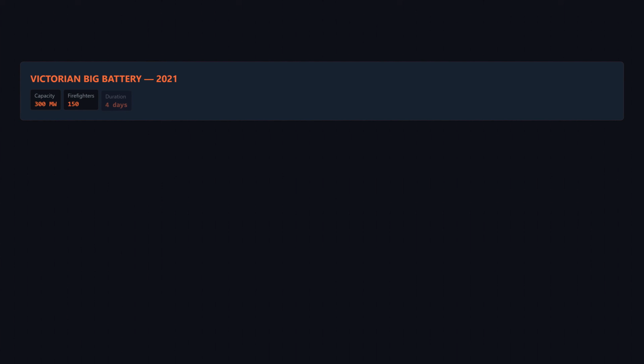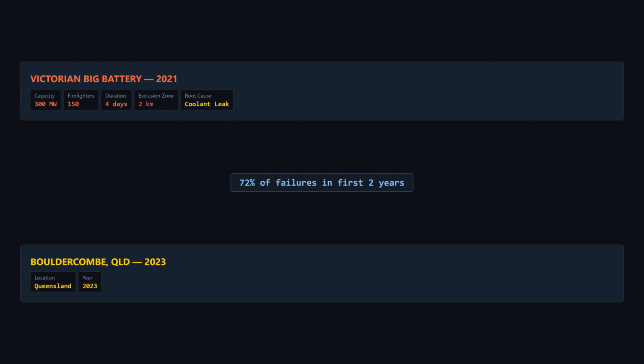July 2021. Victoria's Big Battery near Geelong. A 300 megawatt Tesla Megapack installation, one of the largest in the world. During commissioning, a coolant leak in one Megapack triggered thermal runaway. The fire spread to an adjacent unit. 150 firefighters responded. It burned for 4 days. Two Megapacks were destroyed. The CFA found that the fire couldn't be extinguished. They had to let it burn out while protecting exposures. Toxic gas emissions forced a 2-kilometer exclusion zone. A year later, Queensland's Bouldercombe BESS caught fire during testing.